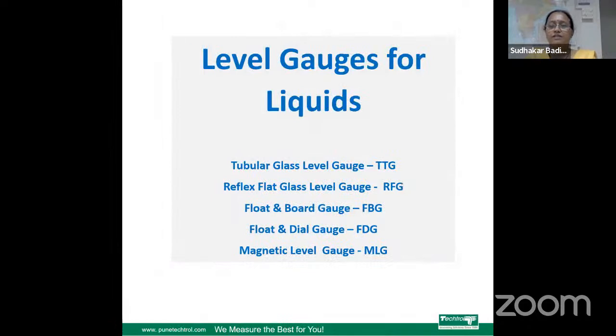So we'll see level gauges for liquids. So first two are glass gauges, that is tubular glass level gauge and reflex flat glass gauge. Then the float type gauges, in that we will see float and board gauge, float and dial gauge, and magnetic level gauge.